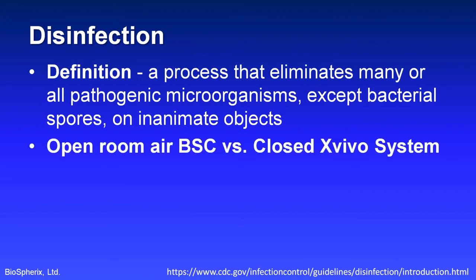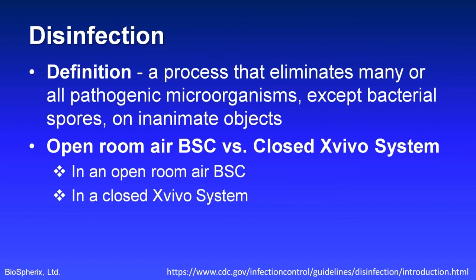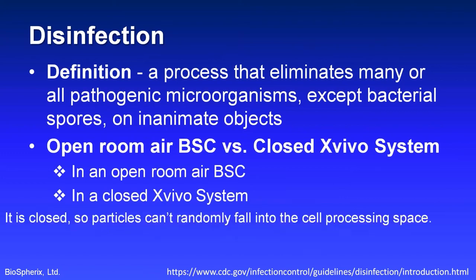Disinfection in an ex vivo system is completely different from an open room-air BSC. In an open room-air BSC, we were taught to spray the disinfectants everywhere and whenever, and keep spraying, because wet time is critical for efficacy. However, the ex vivo system is fundamentally different because it is closed, so particles cannot randomly fall into the cell process space.